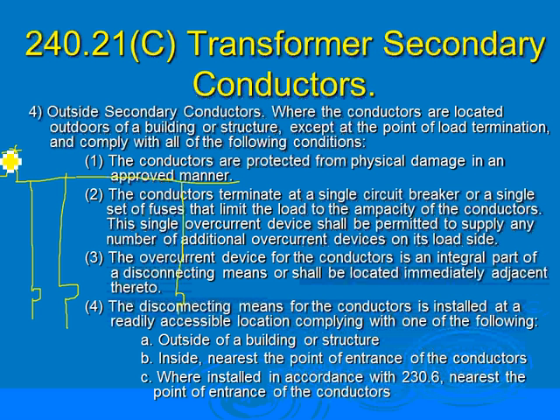You do it by something called the damage curve for conductors. Every conductor, guys, every conductor has 2 ratings. Has anybody heard about the damage curve for conductors? Let's just say a 500 kcm conductor. A 500 kcm conductor can carry 380 amps continuously, forever, right? But how much short circuit current can a 500 kcm carry, and for how long? That's the damage curve for the conductor.